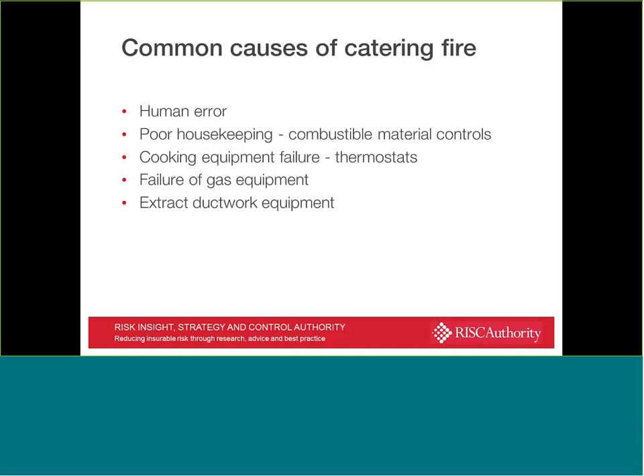But in terms of the common causes of fire, I've put a few on the screen there. Human error, obviously, people doing things wrong, people not doing things right, which can often be different things entirely. Poor standards of housekeeping, not just in terms of cleaning of ductwork, but in the environment generally, and ensuring that the volumes of combustible materials are minimised and that they're kept clear of ignition sources, just basic issues such as that. Failure of cooking equipment, with thermostats not working effectively or overheat devices not properly functioning or tested or maintained. Failure of gas equipment, of course, albeit we're not necessarily going to focus on that. And then, of course, the extract ductwork equipment itself, and in particular the standards of cleaning, and in some instances its design, its layout, and the type of equipment that's actually being used.